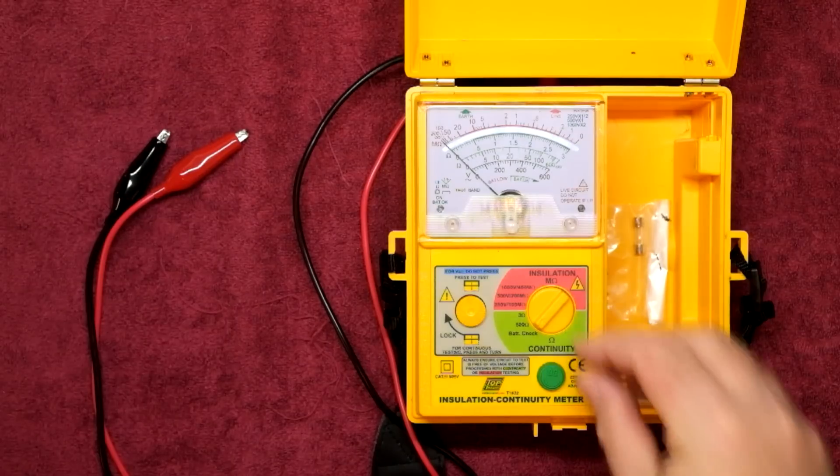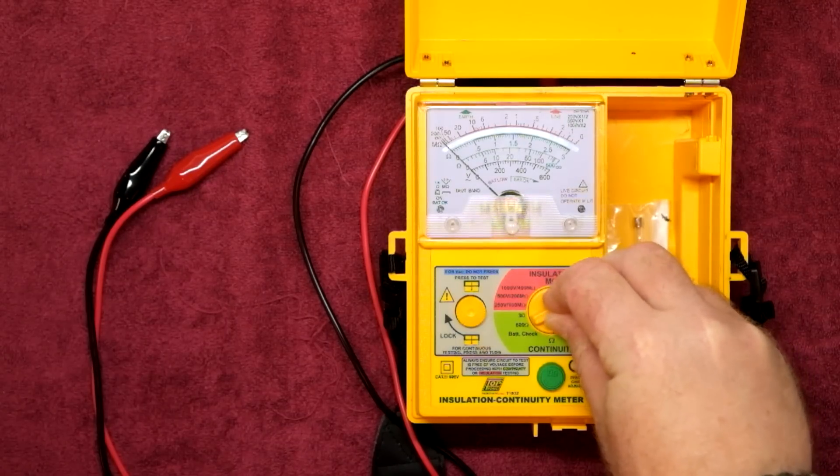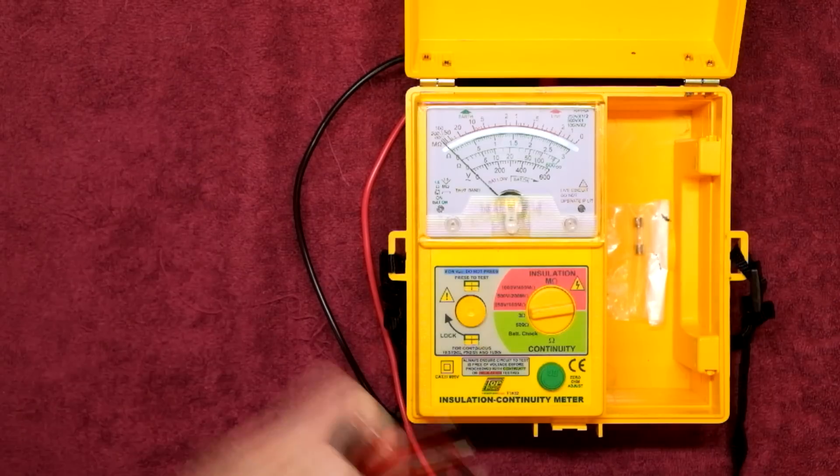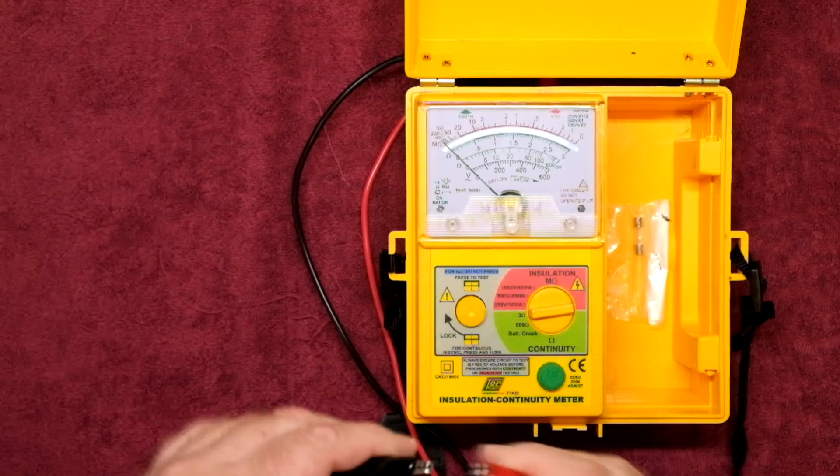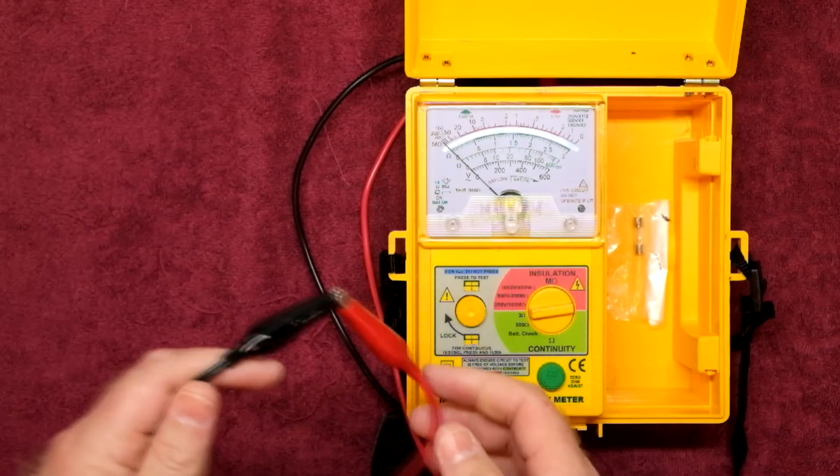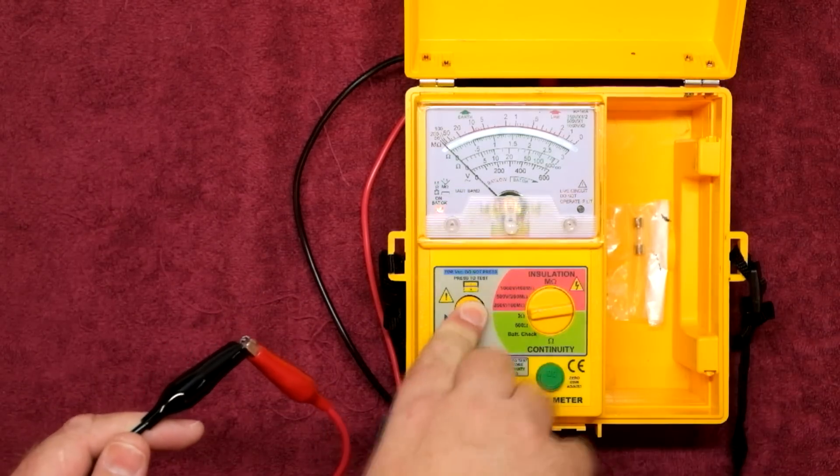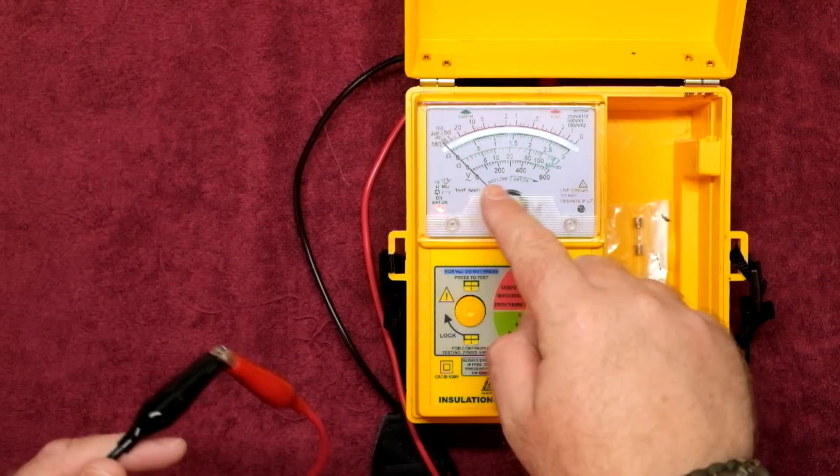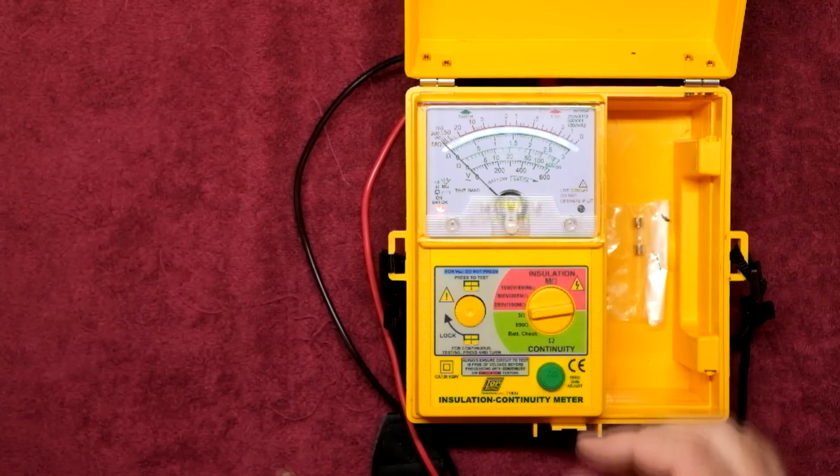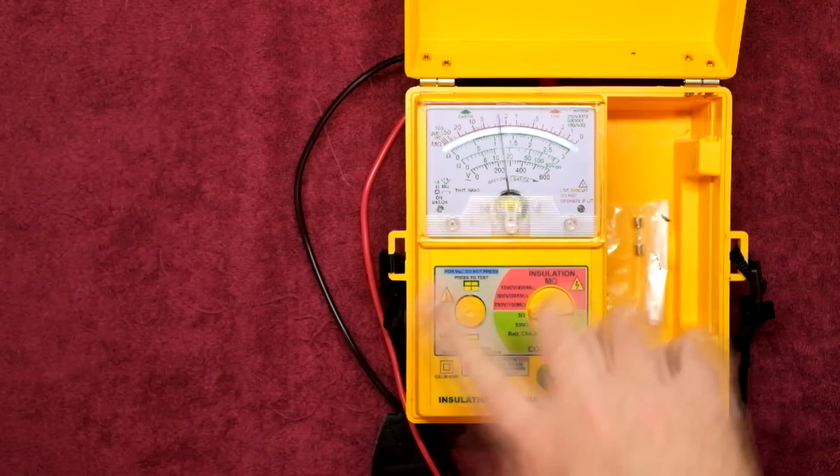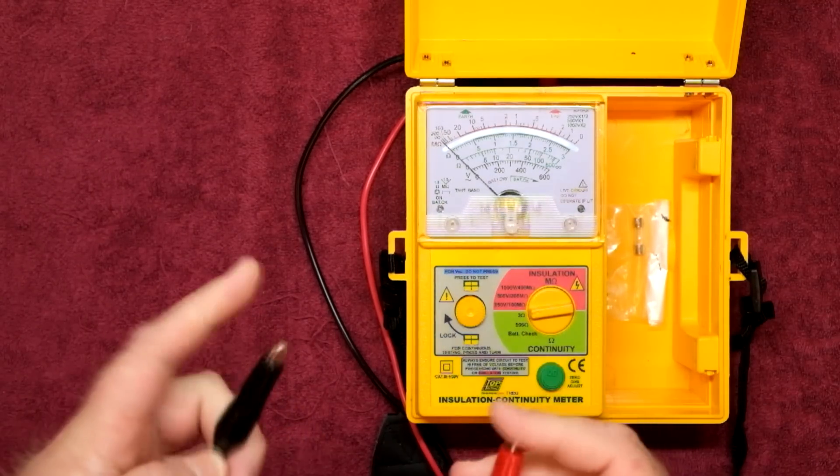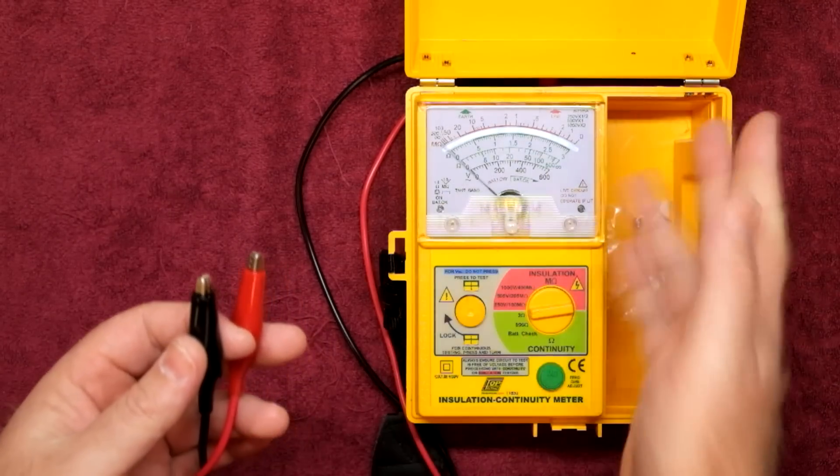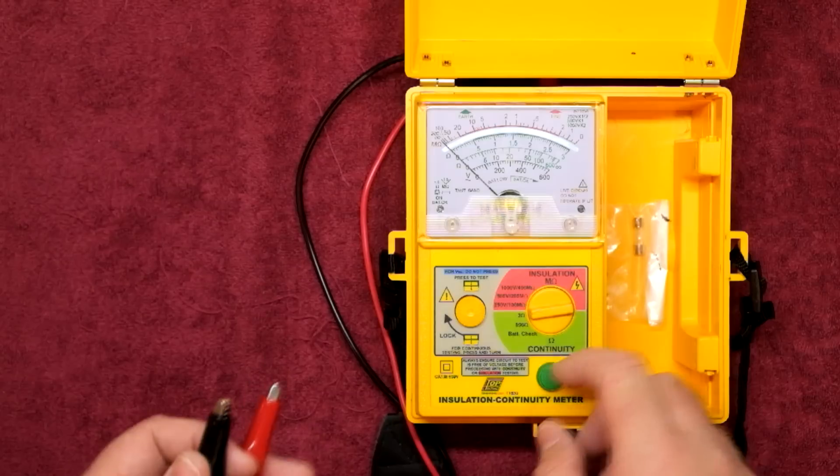Now there's a few little catch-22s with this. If you wanted to do a resistance test at say 500 ohms or let's just say the 3 ohm scale, you would first need to calibrate it. So you would clip your clips together, push the button and then you could actually calibrate this to a zero reading on the display. Once you've done that it's now ready for resistance testing. So you could basically clip that on, push the button and we'll measure up to 3 ohms or up to 500 ohms over here.